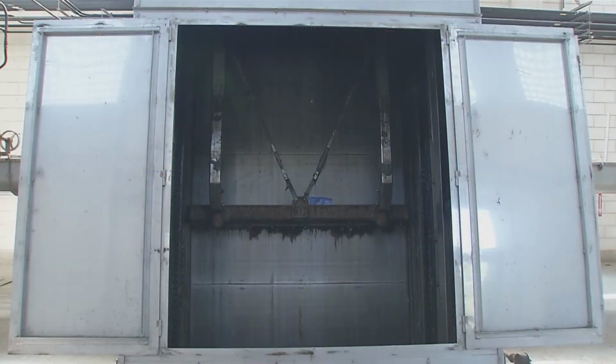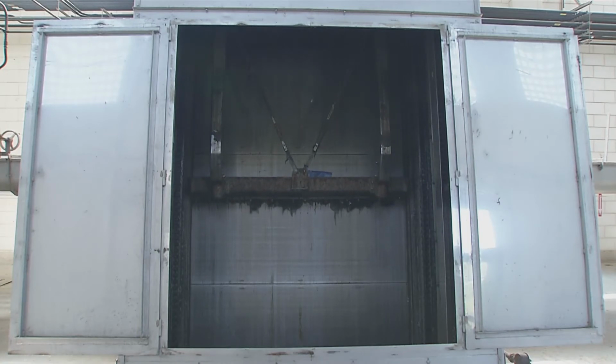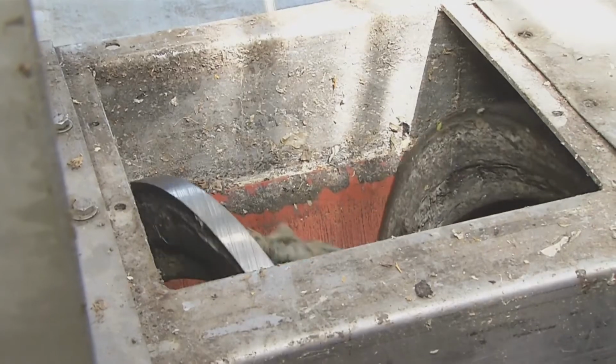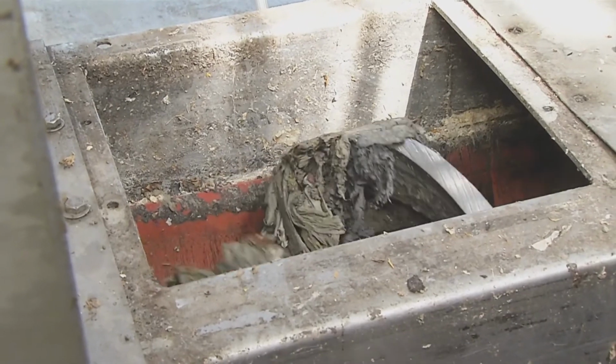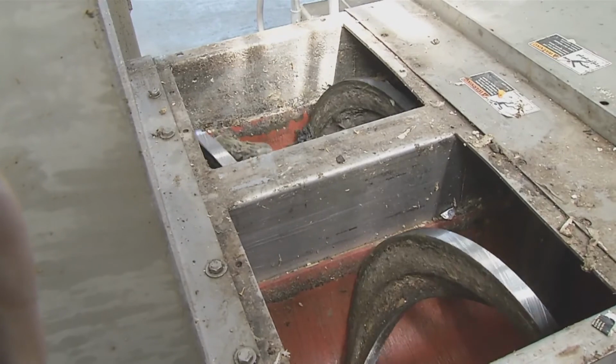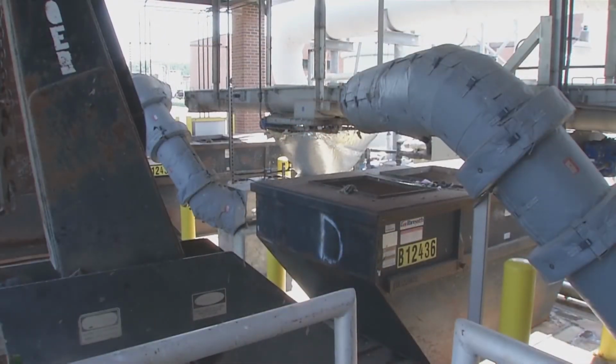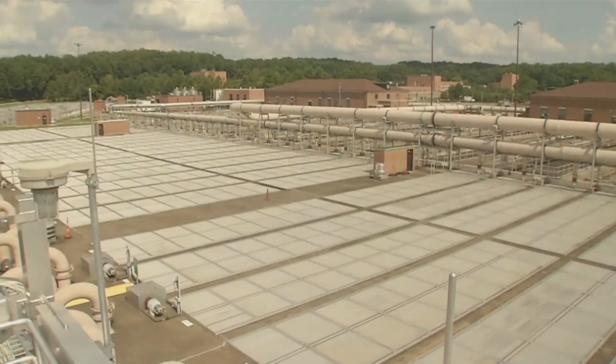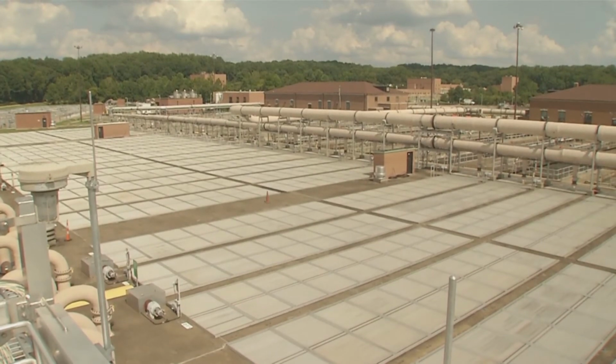At the wastewater treatment plant, we have a preliminary treatment process. These are the bar screens. They remove bulk trash that could damage our plant if they entered the system. These unflushables represent all of the plastic that we added to our tank. When wastewater continues through the bar screens, it enters our primary clarifiers. These are large settling tanks. This is what your tank is now representing.